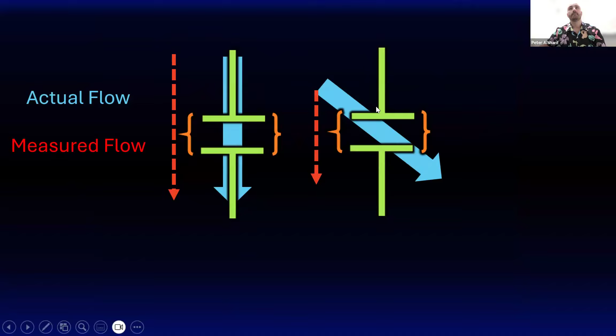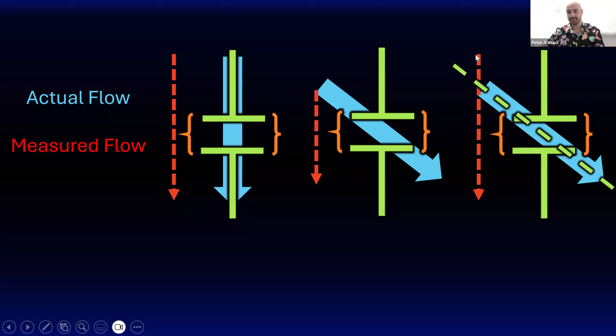But how often do you get flow that's moving towards and away from the probe? A little bit inconvenient. The machine allows you to do this thing called angle correction. In this case we don't have a good angle, right? The flow is not in the same direction as the green line. But you get this little dotted line that comes up, and you can change the angle on that dotted line, and the machine will do trigonometry to figure out what the flow would be expected, your sine, cosine, etc.